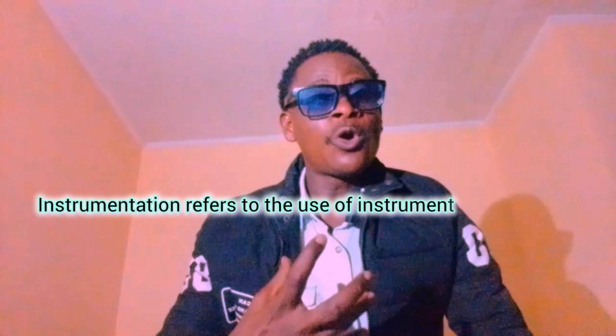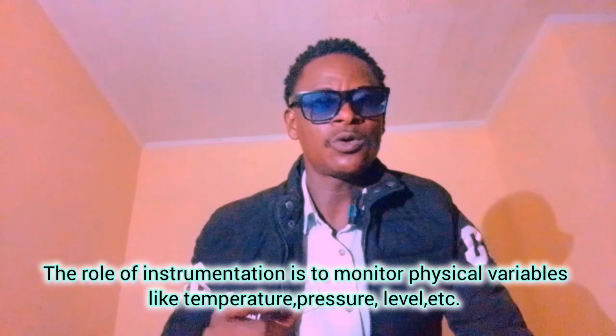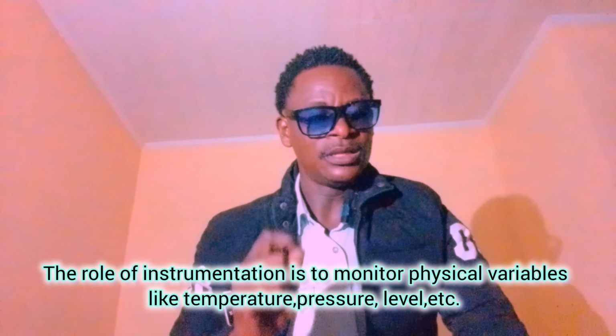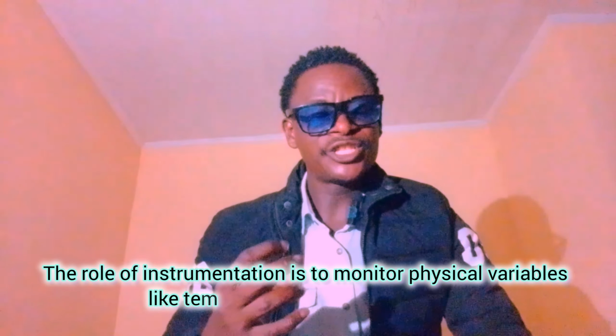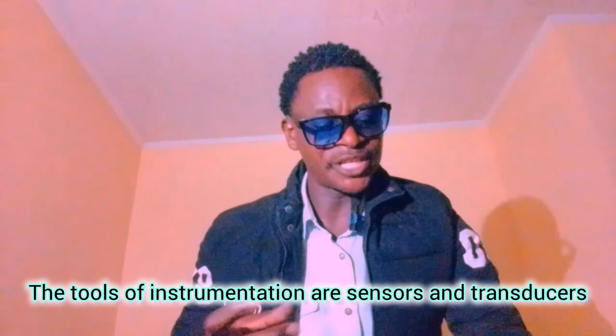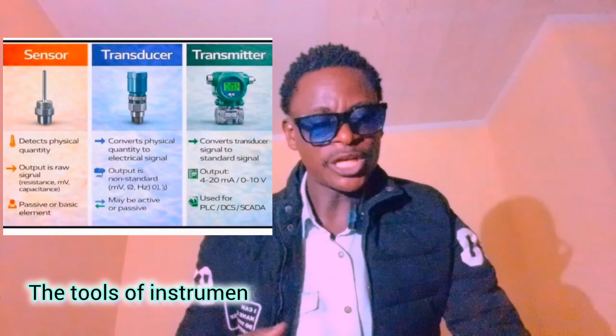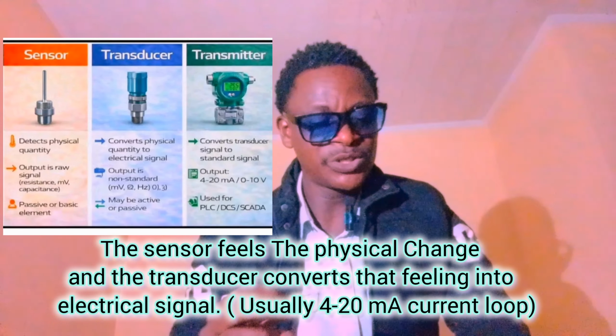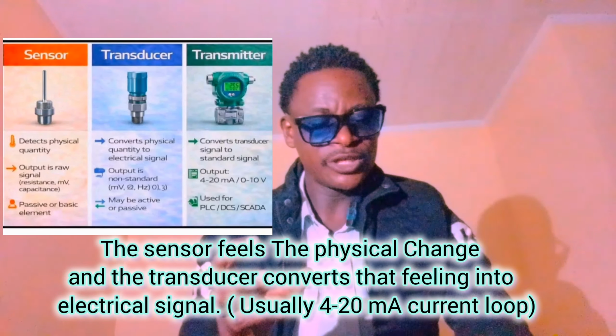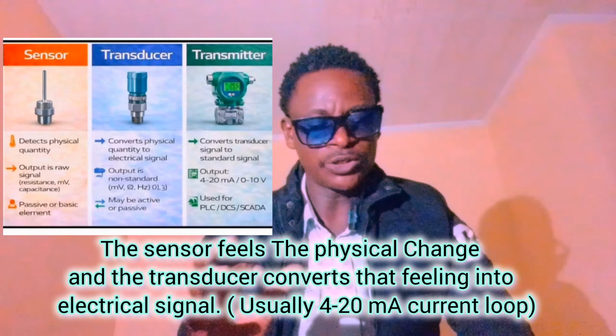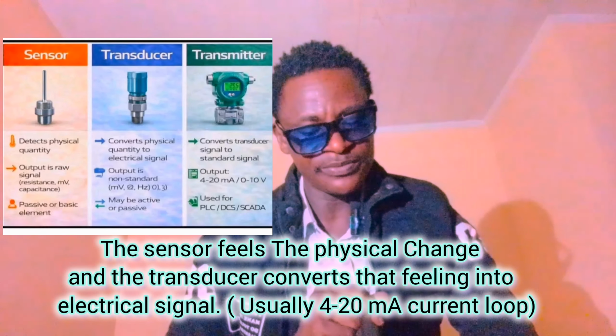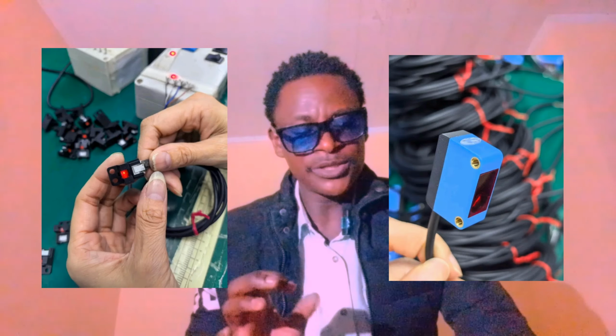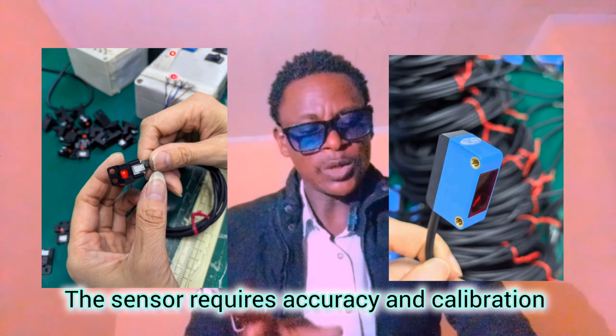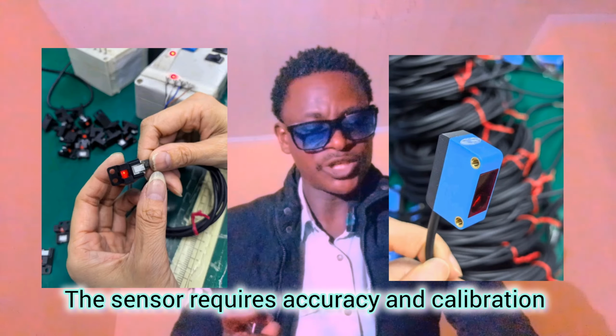Now, what is the role of instrumentation? The role of instrumentation is to monitor physical variables like liquid level or gas pressure. And the tools of instrumentation are sensors and transducers. The sensor feels the change and the transducer converts that feeling into an electrical signal, usually 4 to 20 milliamps current loop. So the sensors require accuracy, which is the closeness to the true values, and calibration, that is adjustment to ensure accuracy.